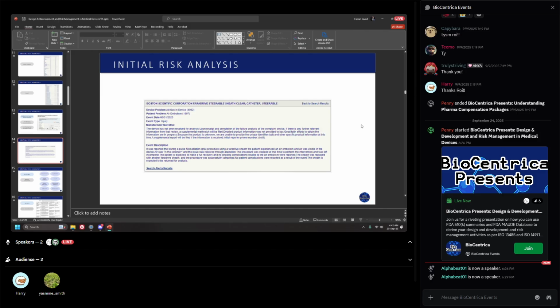Using these early on and building them into your quality management system will help you keep everything consistent. So even if your device is evolving over time, or if you have more devices, once you update them or continue the development, you will be adding new errors or warnings which didn't exist before. So using these standardized terms removes the dependency on your errors and warnings dictionaries. So you can actually compare what you had 5 years ago to what you have now with the same dictionary.